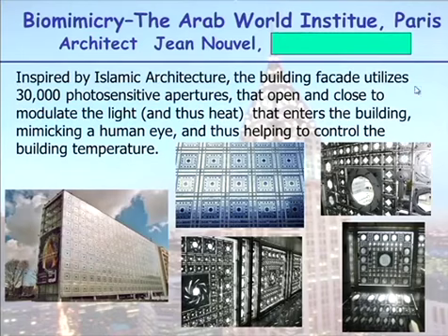The building facade utilises 30,000 photosensitive apertures that open and close to modulate the light and the heat that enters the building, mimicking a human eye. We all know that our eyes get bigger or smaller, the pupils, depending on whether you're outside or inside. If you sit there on a sunny day when it gets shady and sunny again, you'll see this facade moving. The apertures open up and they close. Here they are in an open position, and it's got fantastic shading into the building.